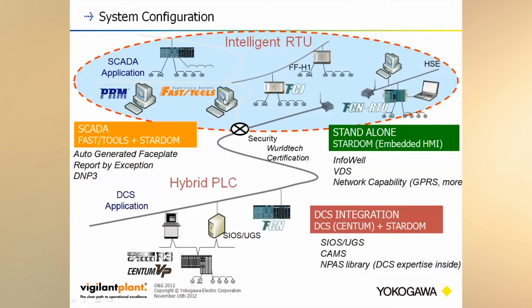We also have tight integration into our SCADA package, called Fast Tools. So if we have, say, PID loops deployed up here, we can very quickly and automatically build them in - almost a little bit like a DCS, where we take the hardware at the bottom level and automatically generate our faceplate system. For people familiar with Yokogawa's Centum system, or even other DCSs, it's very common to take PIDs generated in your control package and pop them up right on your supervisor package. So we've got a nice combination there. And over here, we're showing foundation field bus connectivity from an FCJ.